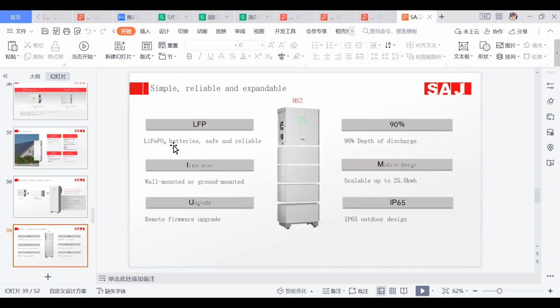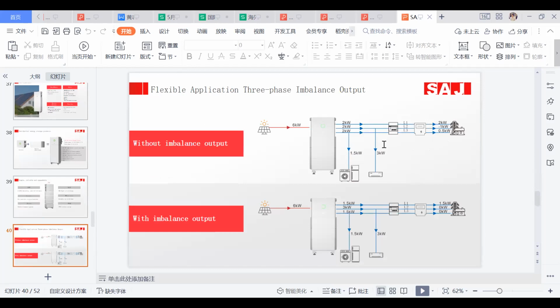And the batteries are also lithium batteries, and the depth of discharge is 90%. Our 3-phase inverters support 3-phase imbalance output. That is, on each phase, we could support different power. For example, when on one phase the load is 1.5 kilowatt, and on the other phase you have a 3 kilowatt load, you don't need to export 3 kilowatt on every phase to support the loads. You could only support 3 kilowatt on this phase and 1.5 kilowatt on the other phase to save your energy.